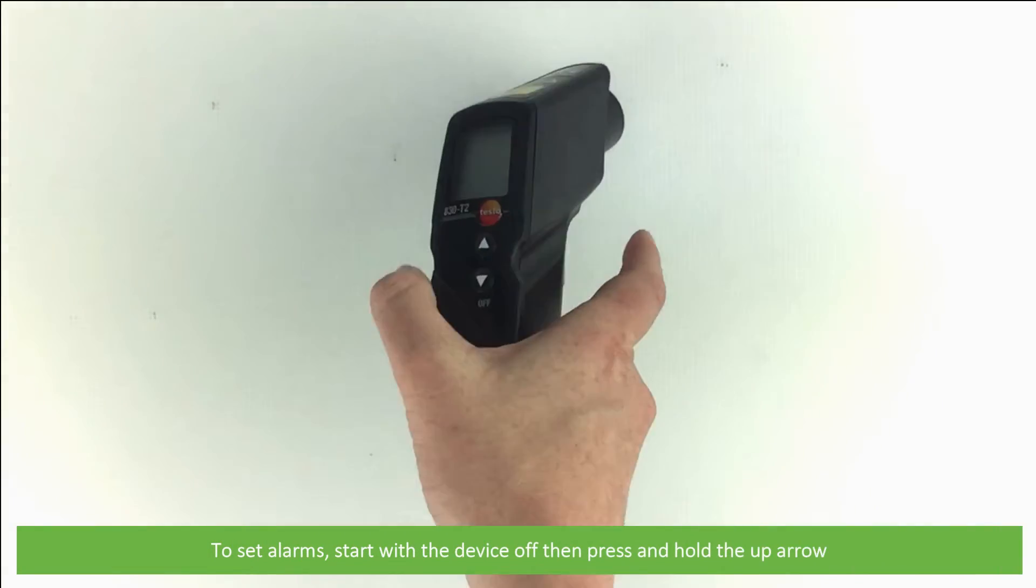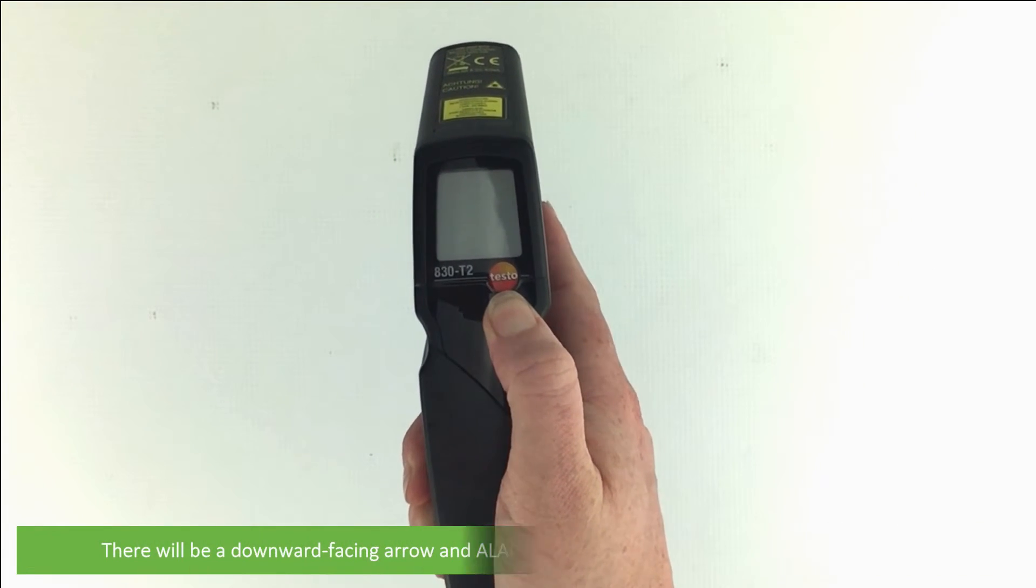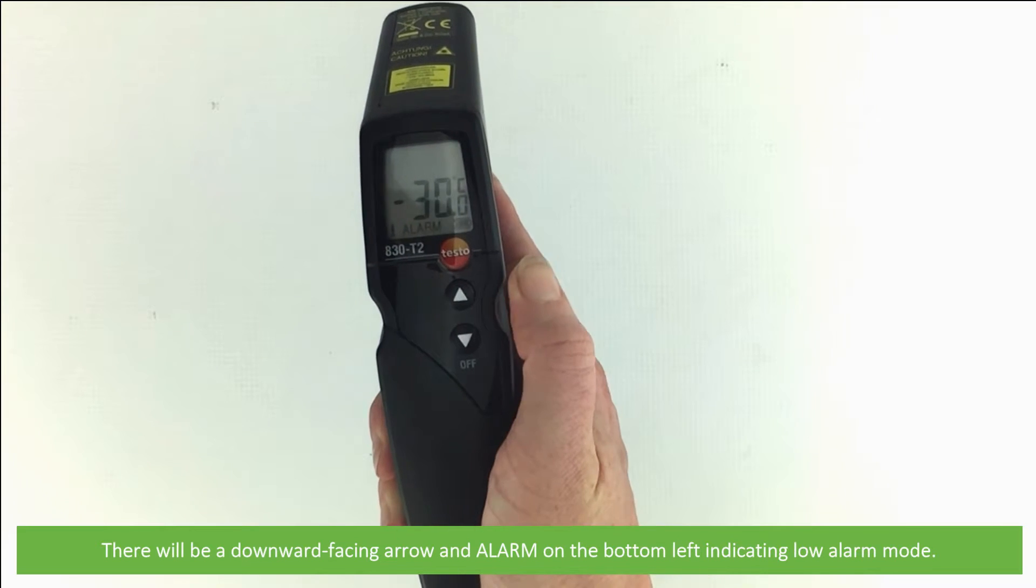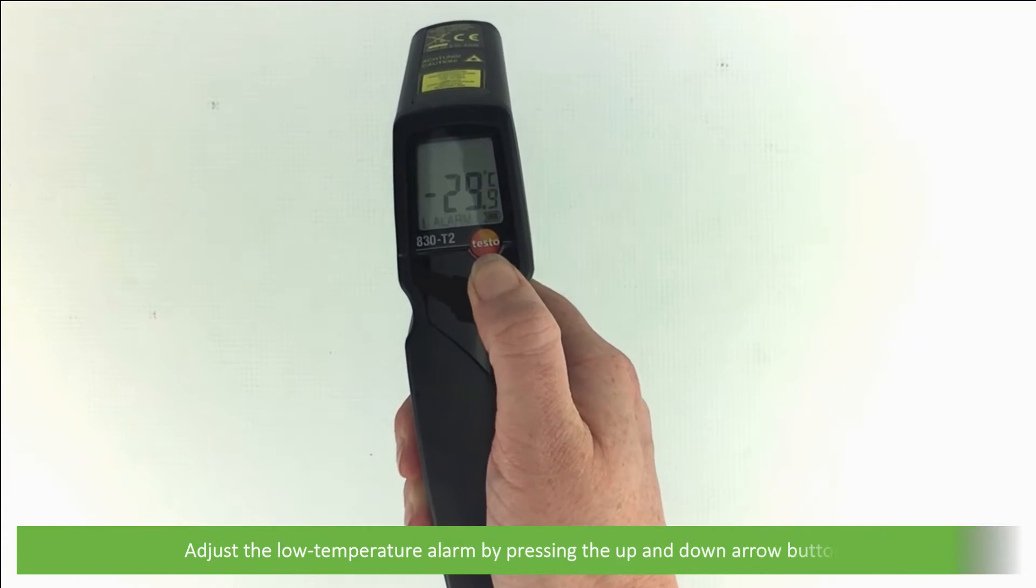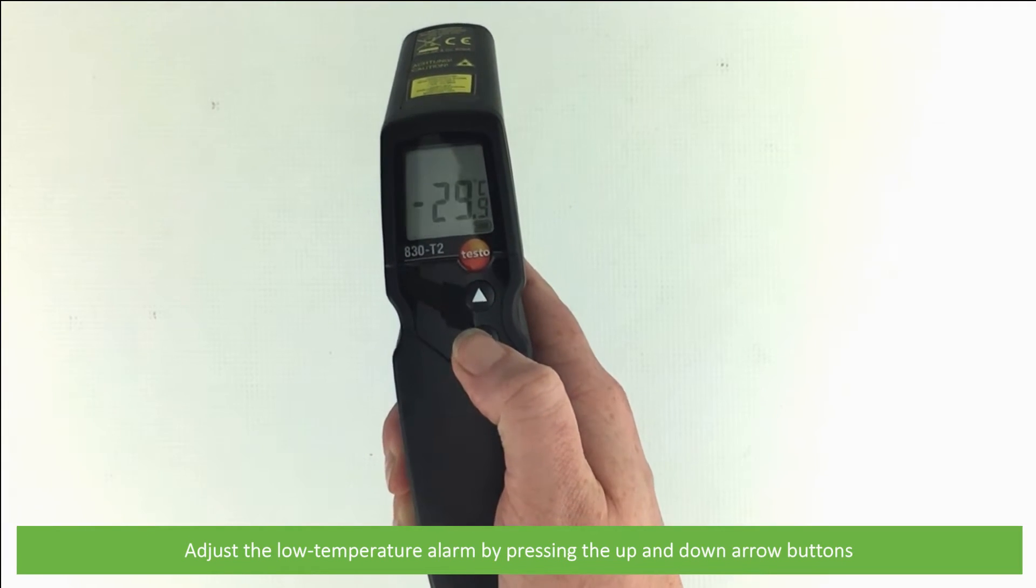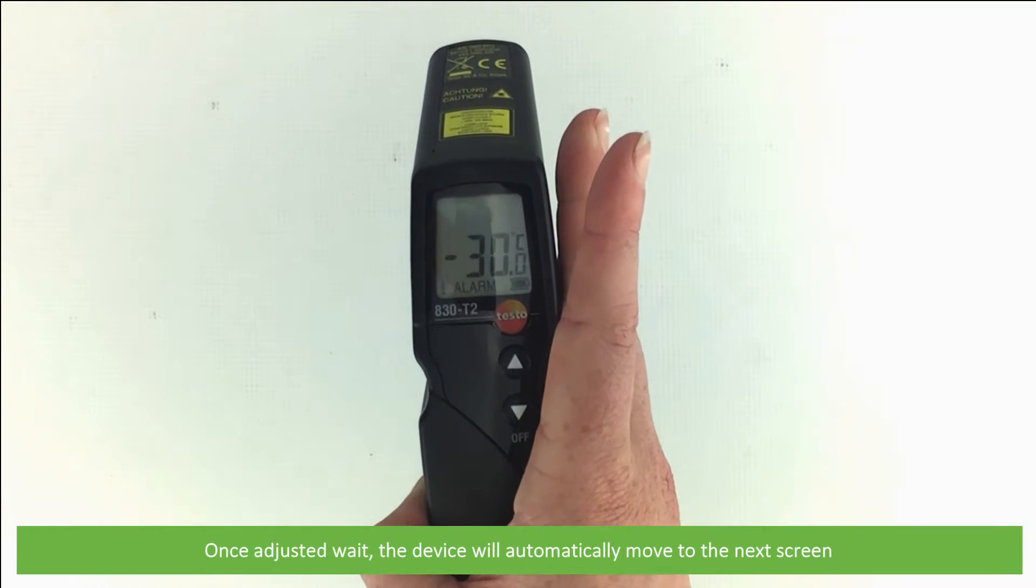To set alarms start with the device off then press and hold the up arrow. There will be a downward facing arrow and alarm on the bottom left of the screen indicating low alarm mode. Adjust the low temperature alarm by pressing the up and down arrow buttons. Once adjusted wait. The device will automatically move to the next screen.